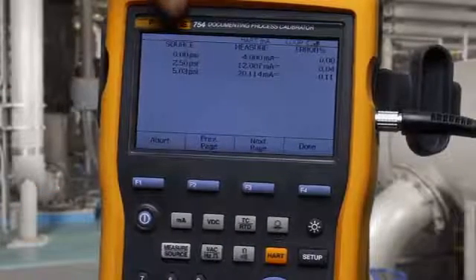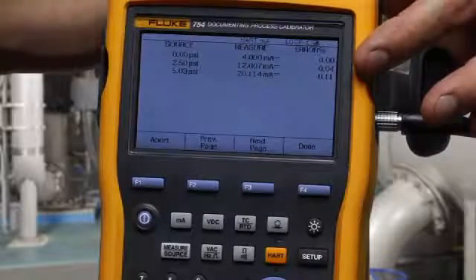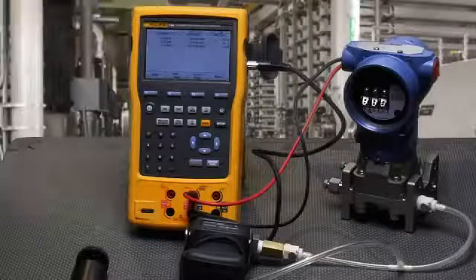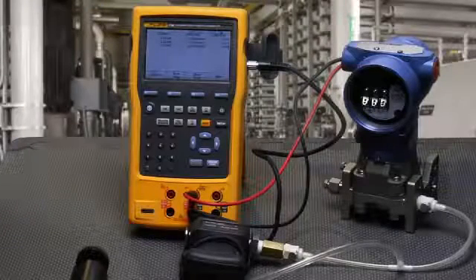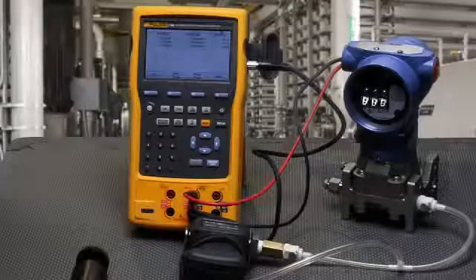You see the applied pressure measured milliamp. And in this case, all the errors are less than 0.25% and the test passes. And that is how you calibrate a Rosemount 3051 HART Smart Pressure Transmitter using the Fluke 754 Documenting HART Process Calibrator.